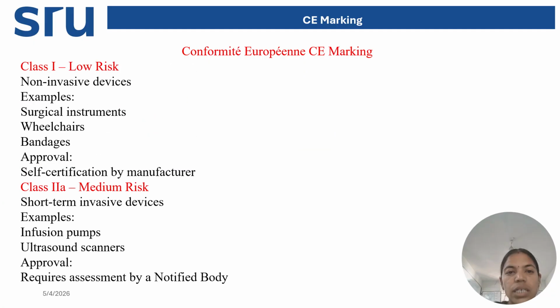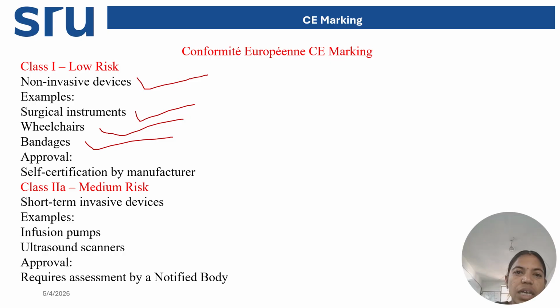First one is class 1. It is a low risk category. So all the non-invasive devices. Invasiveness is the degree of contact with the human body. Non-invasive medical devices do not get physical contact with or pierce into the human body. Examples: surgical instruments, wheelchairs, bandages. All these come under classification 1, that is, class 1 low risk category. For this, the approval is self certification by the manufacturer.